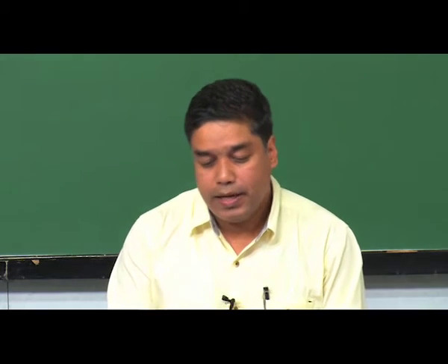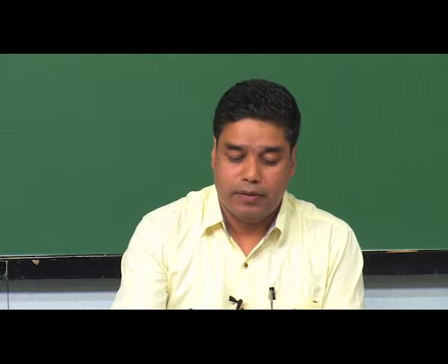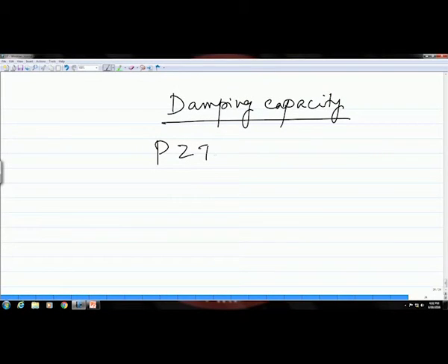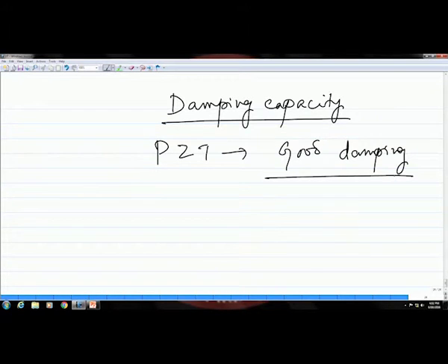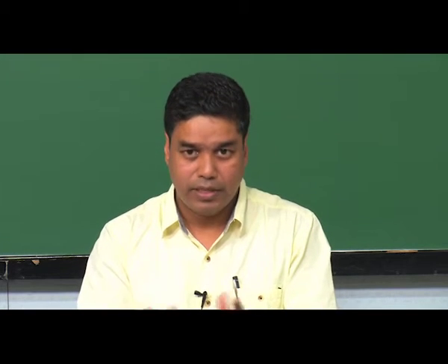So, PZT is a very good damping material. So, apart from the piezoelectric property, it also has good damping, and in most of the cases, to enhance this damping, a damping backing is provided in the housing in which this element is there. So, when you talk about the construction of this ultrasonic transducer, we will talk about that also.